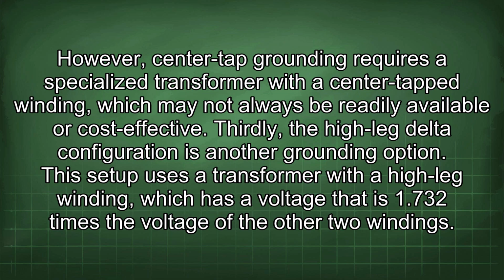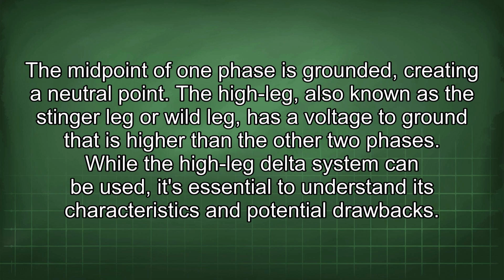Thirdly, the high leg delta configuration is another grounding option. This setup uses a transformer with a high-leg winding, which has a voltage that is 1.732 times the voltage of the other two windings. The midpoint of one phase is grounded, creating a neutral point. The high leg, also known as the stinger leg or wild leg, has a voltage to ground that is higher than the other two phases.